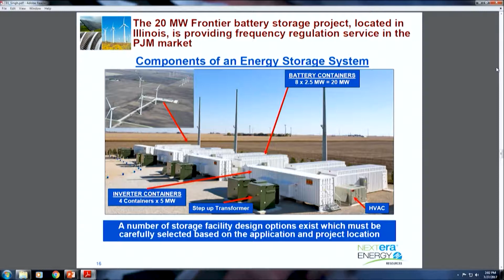Here's a picture of one of our systems, in Illinois, a 20 megawatt system, to show you what it looks like. You've got 8 containers in back, 2.5 megawatts each worth of batteries. Within each container you'll have a fire suppression system, air conditioning, and control systems. The 4 boxes in front are inverters, 5 megawatts each. Then you have a step-up transformer, and the voltage gets stepped up to 34 kV, and then 138 kV in this case, before it goes to the grid. Typically, that's how the system works.